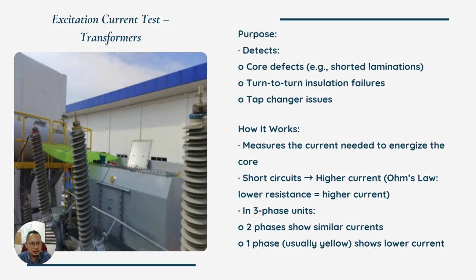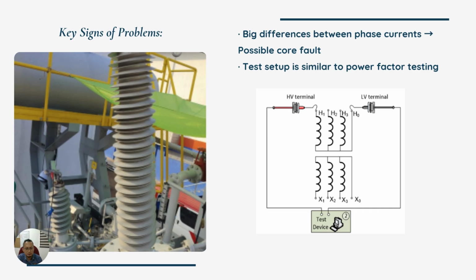Another important test is the excitation current test. This test detects core defects, insulation failures, and issues with the tap changer. It works by measuring the current required to energize the transformer's core. If there are short circuits, the current increases due to lower resistance. The key indicator of potential issues is when there's a significant difference in current between the phases of a three-phase unit, particularly when one phase shows a lower current. This is the sample test, set up similar to power factor testing.